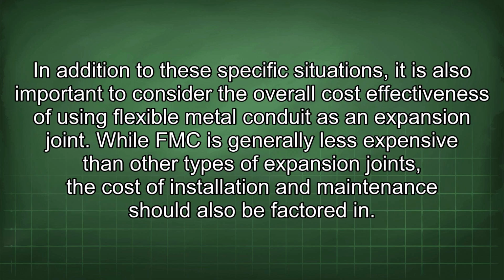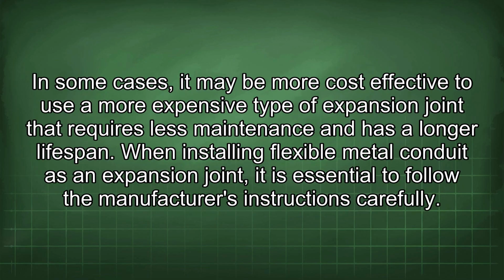In addition to these specific situations, it is also important to consider the overall cost-effectiveness of using flexible metal conduit as an expansion joint. While FMC is generally less expensive than other types of expansion joints, the cost of installation and maintenance should also be factored in. In some cases, it may be more cost-effective to use a more expensive type of expansion joint that requires less maintenance and has a longer lifespan.